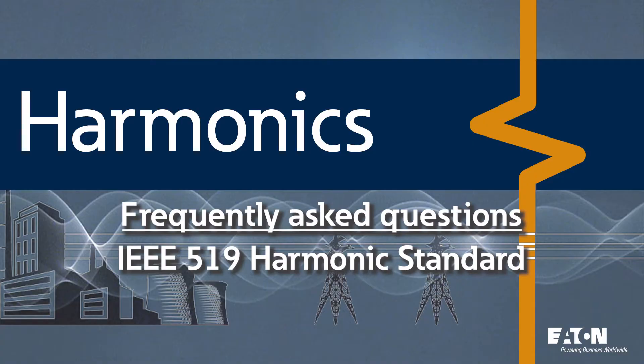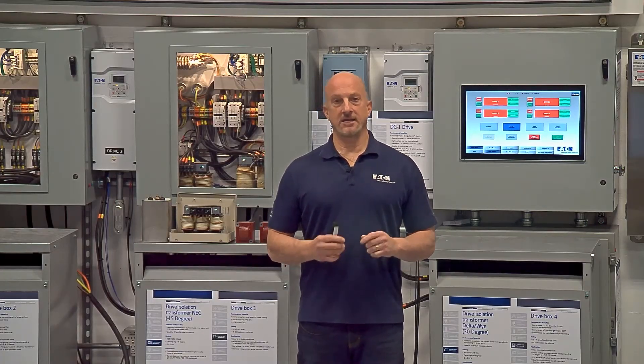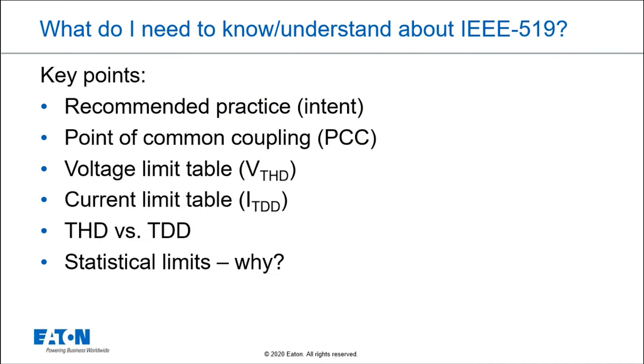One of the questions we get a lot is how does IEEE 519, the standard that deals with harmonics, relate to me and what do I need to know about it? First thing is that this is a recommended practice, so the intent is that it's supposed to guide you. It's not supposed to be very strict rules, and utility companies typically don't enforce it unless required by neighboring customers and things that cause problems.